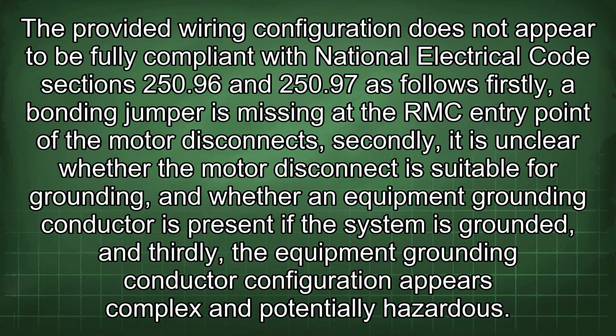The provided wiring configuration does not appear to be fully compliant with National Electrical Code Sections 250.96 and 250.97 as follows. Firstly, a bonding jumper is missing at the RMC entry point of the motor disconnect. Secondly, it is unclear whether the motor disconnect is suitable for grounding, and whether an equipment grounding conductor is present if the system is grounded. And thirdly, the equipment grounding conductor configuration appears complex and potentially hazardous.